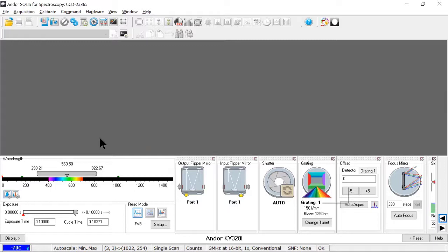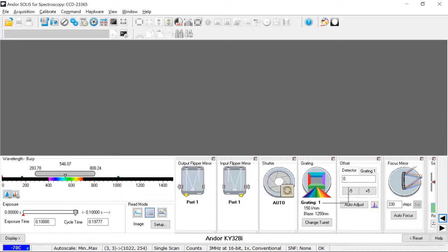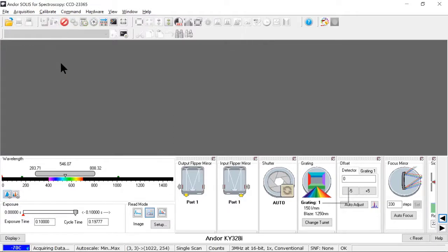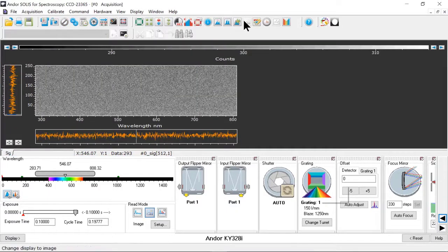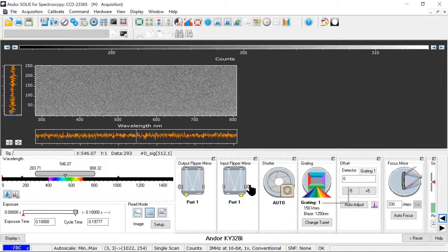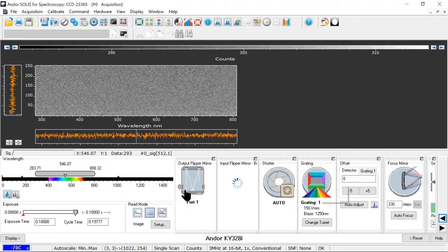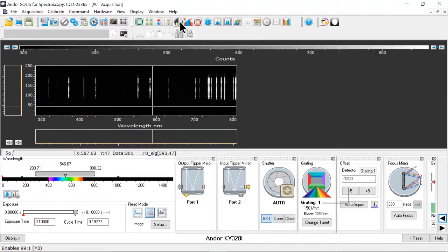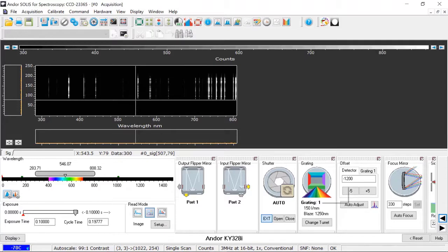So let me demonstrate a quick data acquisition. First, I'll record an image. So I'll set this to image. I'll aim for one of the mercury lines. Record an image. And I noticed that I haven't set my input flipper mirror directly. So I'm going to set that to get light from my fiber optic cable, which is on my side port. My output flipper mirror is fine because I'm recording from the Newton that's on my direct output port. And once I get this in contrast with this button, you can see that I don't have a single core on my fiber. I actually have many cores. This is a multi-core fiber with a ferrule terminator.